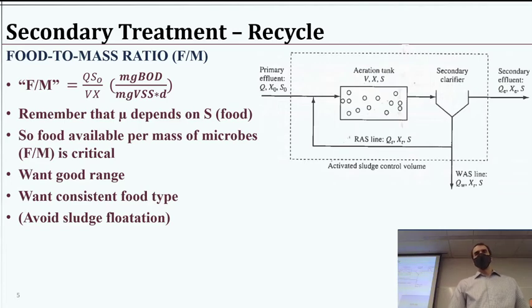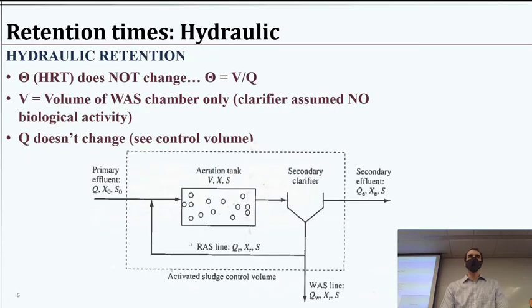Yeah, so the video I showed last time where we saw some layer of sludge, foam stuff on the top, I believe that one was operating pretty normally. You're going to have some floating materials, and usually we call it the scum layer. And that's typical because we just had a process with all this aeration, and some particles are going to have caught onto bubbles and they're going to be floating. There's going to be some amount of that. But the majority of the bacteria will usually settle unless the wrong type starts growing and they grow these filamentous materials, and then they all kind of float up as a blanket, and you're getting clarification, but it's in the wrong direction. Maybe if I have a little extra time here, I'll search for a video and see if we can find that. I haven't seen a video of it myself, but it would be interesting to see what it looks like when you've got that flotation problem. Good question.